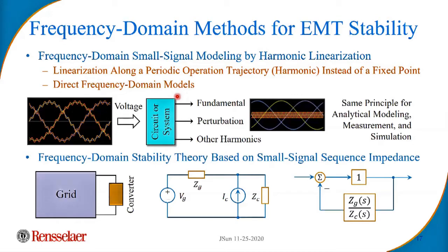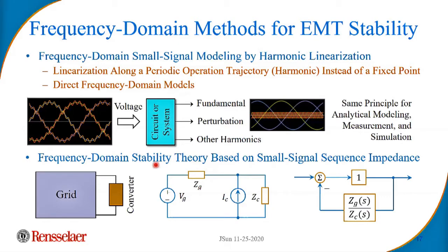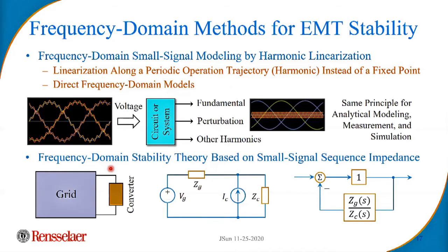In a simple form, these models can be viewed as impedance, but fundamentally they are frequency domain transfer functions, and they allow us to describe converters at their terminals. So we can describe the behavior of individual pieces in this form. The second piece of the framework is system level stability analysis based on impedance. Those who work in power electronics probably recall the earlier work by Professor Middlebrook on impedance-based stability of DC power systems. We expanded that theory to three-phase power systems based on what we call sequence impedance, applying it to three-phase systems using symmetrical components.